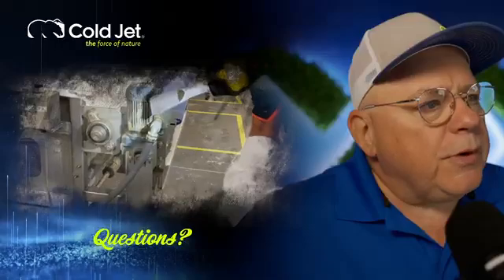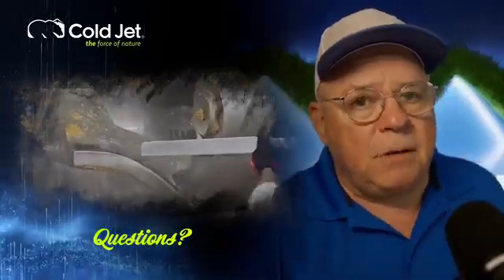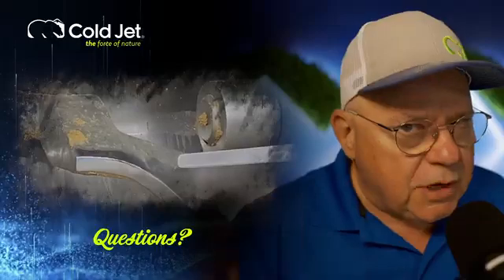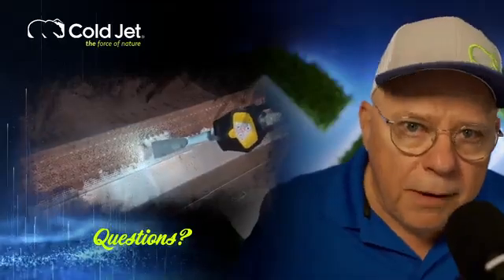Where should the air compressor be installed to reach many areas? Well, if you are a food processing plant, you probably have compressed air piped all over the place. We just have to find the right size airline. To do the big jobs, not micro jobs, you need 130 CFM of air. So you're going to want to get on a 3/4 or 1-inch airline. So you don't need to move the compressor. You simply latch on to the already piped-in air. And our field people can help you with that.